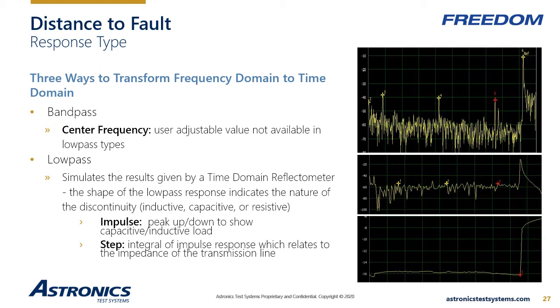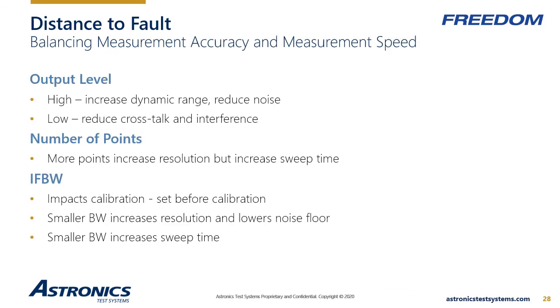Let's take another look at the relevant parameters for the distance to fault tool. This tool has three main parameters. Higher output level allows the VNA to more accurately measure low-level signals. However, in some situations, the high power level may introduce crosstalk or interference into the system. In these situations, the output level should be set to low.